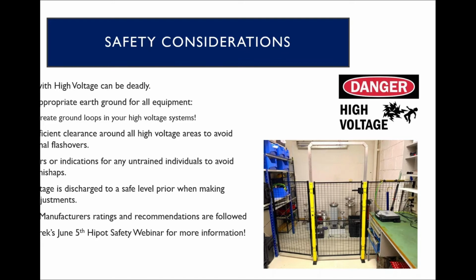It's always a good point to ensure that your voltage is discharged to a safe level prior to making any physical adjustments. You don't want to just grab any wires if you don't know what potential might be on those. So it's always good to check any of your monitoring systems to ensure that there isn't a voltage potential on that cable when you touch it. There are tools for this, such as a discharge rod that you can always use to touch to a high voltage device, as long as it's appropriately rated, to help that process along.